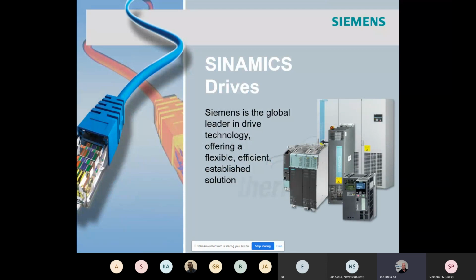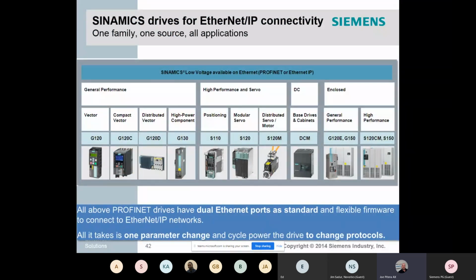One of the major goals of this workshop is to show Siemens' preferred VFD options. The G120 is the bread and butter product, the mainstream drive. Starter is the commissioning and programming software for the entire family. Startdrive is integrated into the TIA Portal and supports many different product families as of version V16. Using the S120 family, we can address any high performance, high demand applications with less than 1 microsecond scan time. This is only supported on PROFINET, isochronous PROFINET.